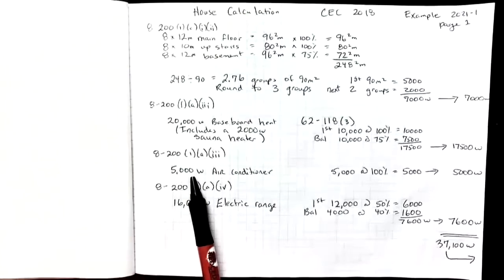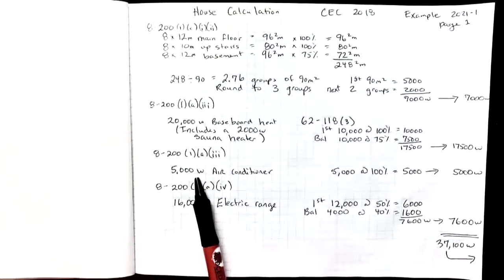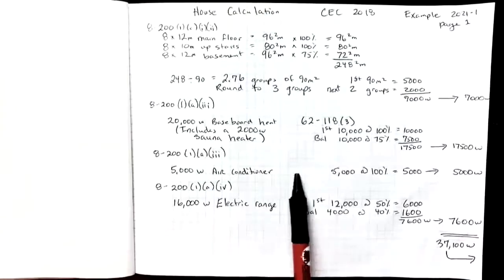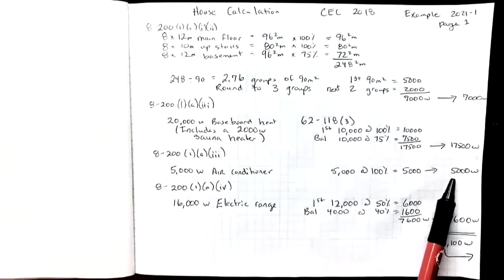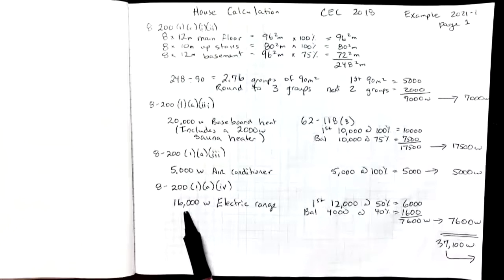Rule 8-200(1)(a) item 3 dictates that we take 100% of the air conditioning demand towards the service. So 5,000 watt air conditioner at 100% means I take 5,000 watts towards the main service.